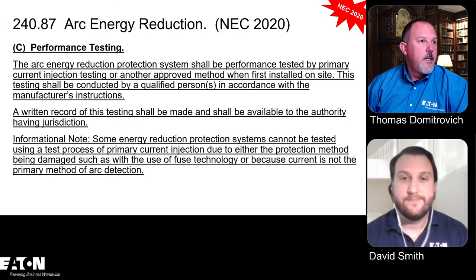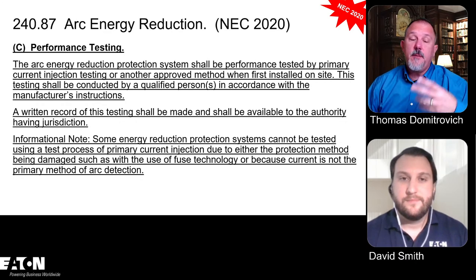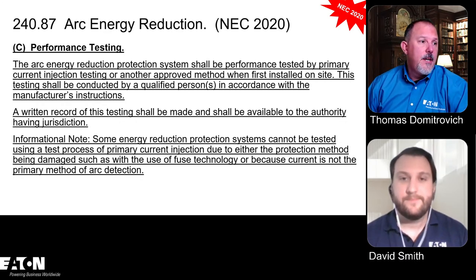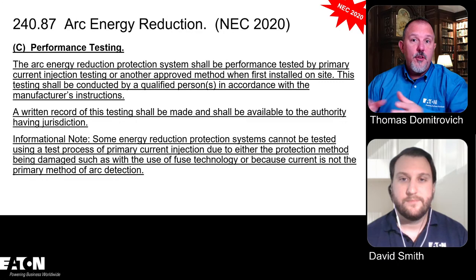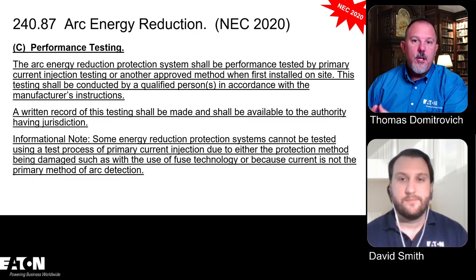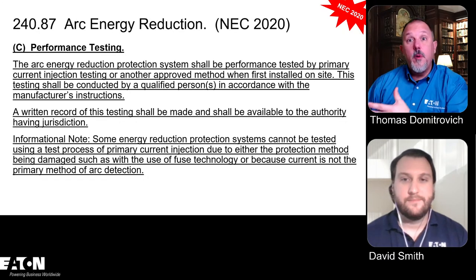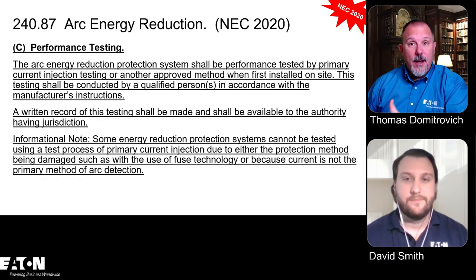Absolutely. And then you have your test reports. You have to check the current transformers. If your system uses external CTs, you've got to make sure the polarities are correct. There are a lot of things that you need to check. But you should have a qualified individual. Make sure that they're qualified on the equipment that they're testing, and they know how to do that, and they can provide you with a test report.